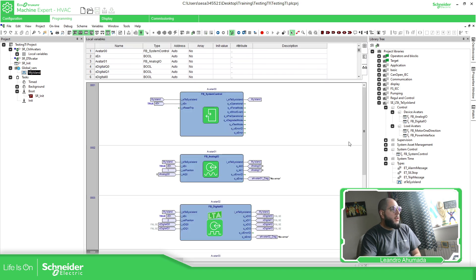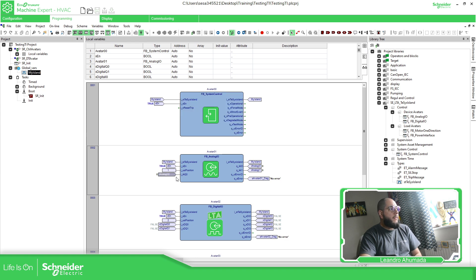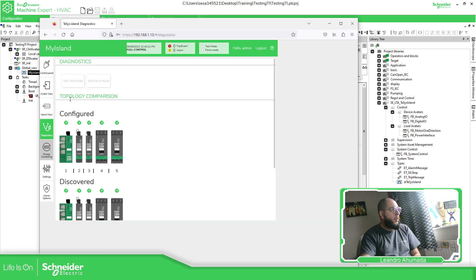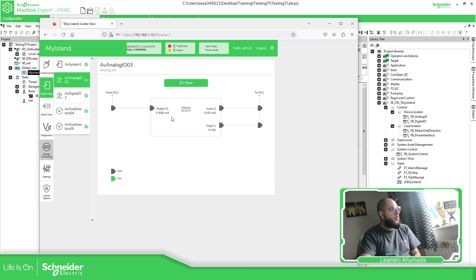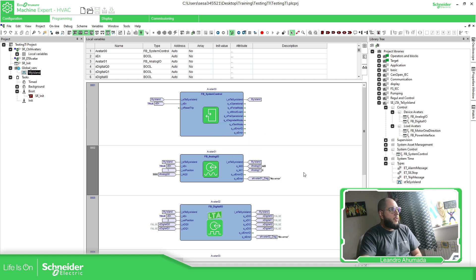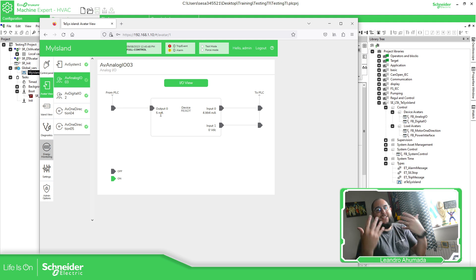Then I have the analog IO. In this particular case, I have the analog IO connected to the analog input. If I select a value like 456, you should be able to see this value or a close value. I'm connecting and sending the data in a loop. Let's go to the avatar view — you should be able to see this information there. As you can see, it's in there. So I'm sending the information. If I press 500 and go back here, you can see 5 milliamps. So you can see I'm really sending and writing information.